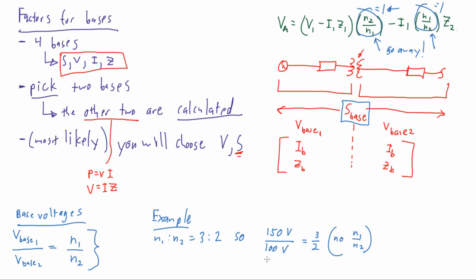What's important to understand and what we're accomplishing here is in each section of a circuit which is divided by a transformer, we're in a sense taking a relationship and applying it to the base. We're taking this ratio relationship that we find in the turns ratio and applying it to each section. And when we apply that relationship to the voltage bases, that means we can get rid of our turns ratio complications. We're building it in, essentially, to the voltage base.